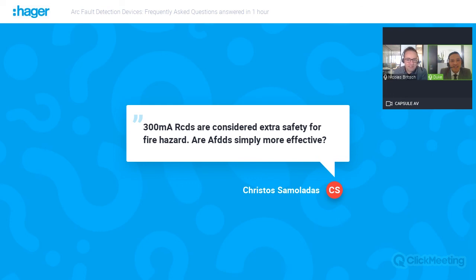300 milliamp RCDs are considered extra safety for fire hazard. Are AFDDs simply more effective? Actually, I can take this question. This is a very interesting question, Christos Samuladas. The function of an RCD is to detect earth faults, leakage earth faults. And the 300 milliamp type is effectively to protect against a level of fire risk, extra safety, as you say. However, AFDDs protect against arc faults, a different type of fault, and today an RCD cannot detect these in most cases. We need the AFDD to complete the protections. But of course, the 300 milliamp RCDs are also effective and efficient.